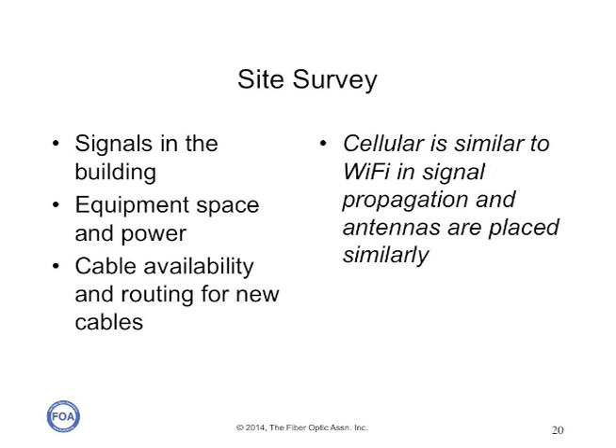Like any network and cabling installation, a site survey is performed prior to the final design. The objective of the survey is to characterize wireless signal propagation within the building and to investigate equipment space and cable routing issues. This building characterization is the basis for system design. Once you know where the head-end equipment will go and where antennas are needed, you can start designing the cable plan. Proper engineering and planning will minimize capital expenditures while ensuring adequate coverage for each of the mobile service providers.